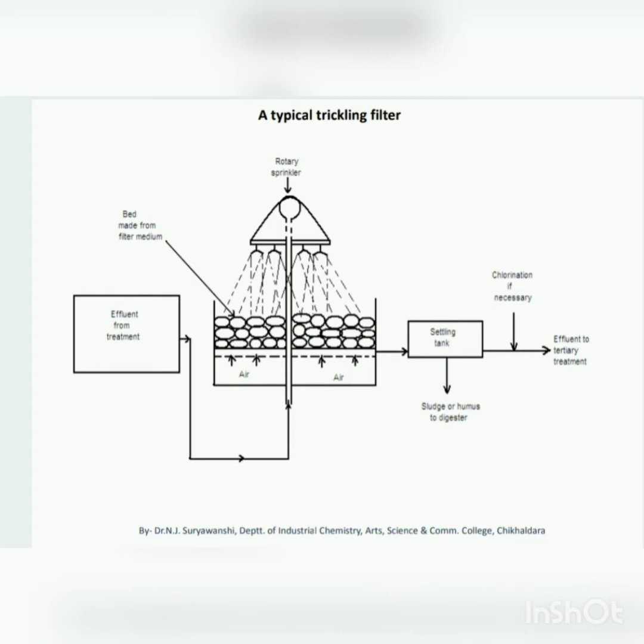Over this, wastewater is sprinkled uniformly on the entire bed with the help of a rotary sprinkler having nozzles. Thus, the wastewater trickles or drips in a small stream through the media. In the filter, there is an arrangement to enter the air at the bottom, counter current to the effluent flow from the media. A gelatinous film containing bacteria and aerobic microorganisms known as zoogloea is formed on the surface of the filter medium, which grows on the nutrients supplied by sewage or the wastewater.